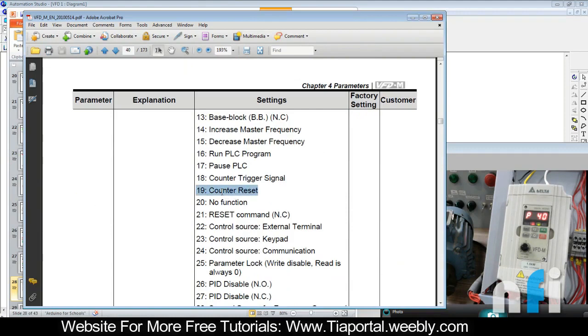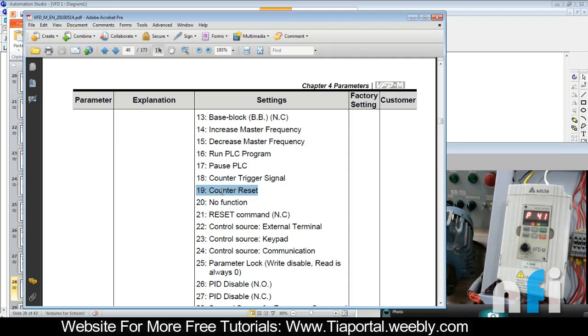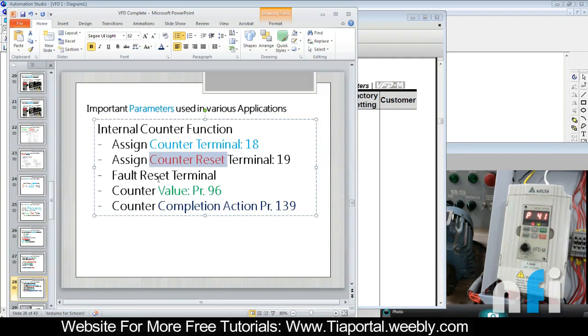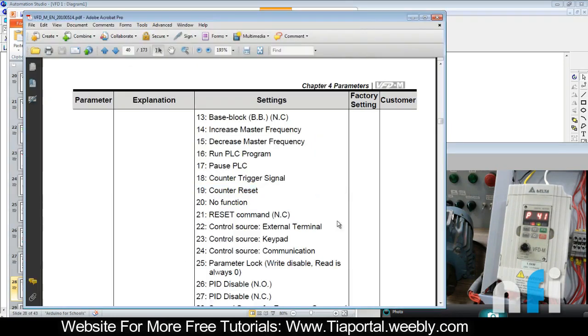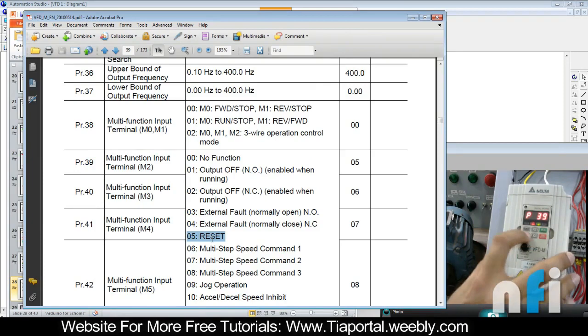Next step is fault reset, because you have a fault which is an external fault that needs to be reset. So we have used terminal M4 to reset the fault. In parameter 41, we have entered 05, so you can see here parameter 41 is 05 to reset the fault, not the counts.